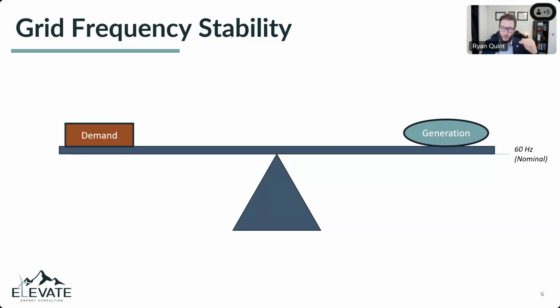As we get more demand relative to generation, frequency starts to drop. The motors have to work harder, and so frequency will start to fall. We plan a system that's able to withstand a certain amount of generation loss, tripping of a large power plant, for example in the West, a couple of nuclear units.